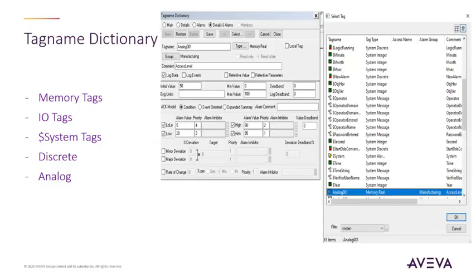We usually need these memory tags if we want to do something internal. For example, let's say I want an internal timer—I do not need to connect to a PLC to have my own timer. I need to create it locally. This is why I need a memory tag to do these internal tasks, with no need to connect to I/O devices.